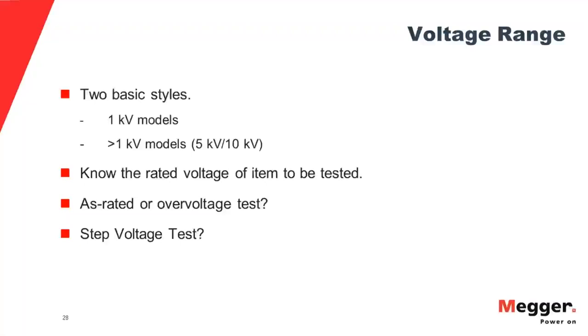Then for industrial and utility type equipment where you go up to higher voltages, you jump to a medium voltage rated tester. So fundamentally, your very first determination in buying an insulation tester will be what is the rated voltage of the equipment that I'm going to be testing, and then select your tester against that. And do you want to do over voltage tests? Think about that. And step voltage tests, we'll talk about that later.